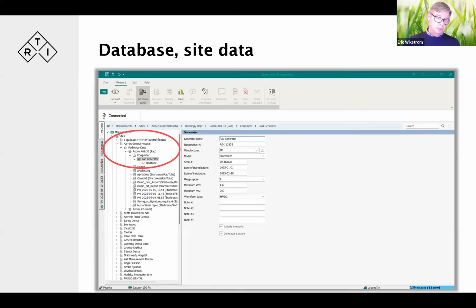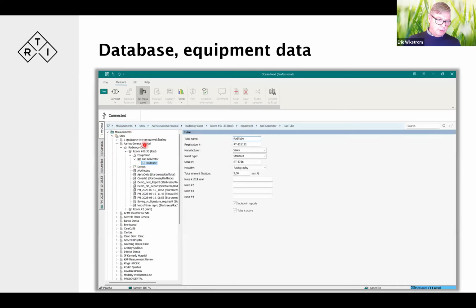Well, since the Ocean software has a database built out of sites, which could be hospitals or clinics, and in each site we'd have departments, a radiology department, for instance, one or more departments. In each department, we can have one or more rooms, and in each room we'll have equipment, and that's typically a generator and a tube. So if we follow this structure, we can then key in the RAD tube with the registration number, if there is one, the manufacturer, standard, the serial number, they all have a serial number, and any other relevant data that we may want to track.